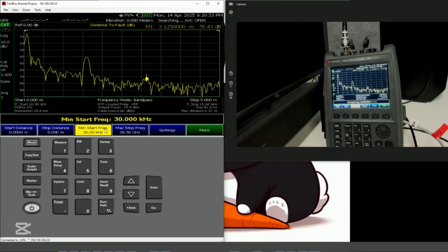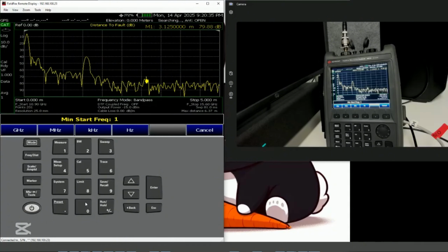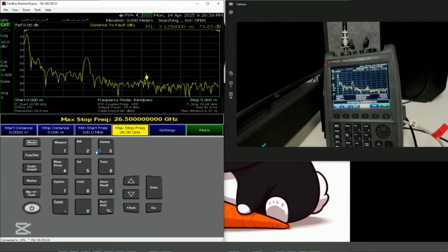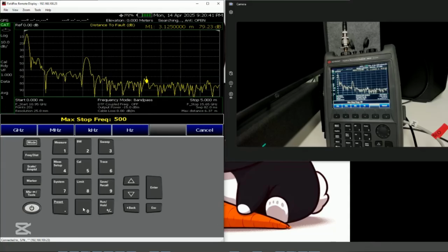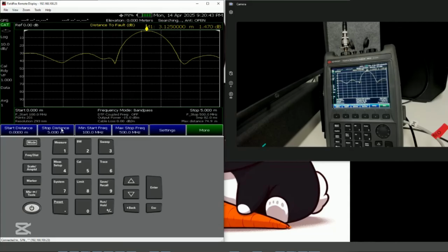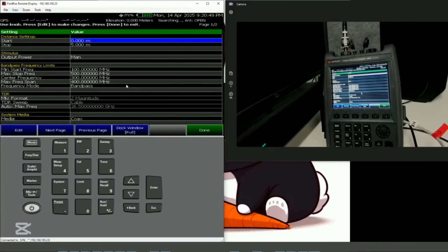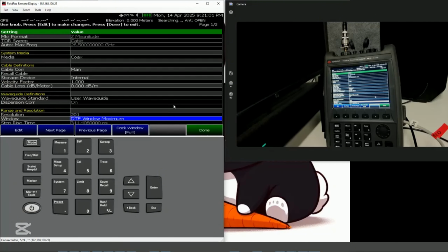So let's give it a try. Let's say we set 100 meg minimum to 500 meg. So let's say that's my filter. You can see the resolution is very bad. So I do recommend for a cable, just go with the low pass, and FieldFox will calculate it based on the best setup.